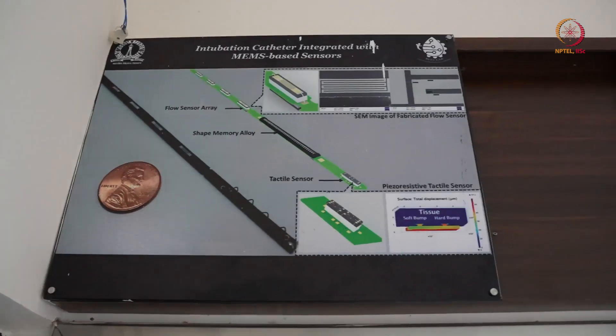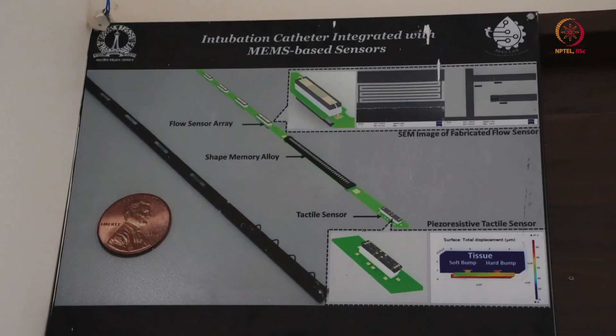Before going inside, from outside we will show some of the work that we have done using this facility. The first image discusses an intubation catheter integrated with MEMS-based sensors. Here we can see a flow sensor array and a tactile sensor which are used for understanding airway choking or airway obstruction. The flow sensor array was implemented by a series of heaters, and the tactile sensor is basically a resistive tactile sensor. These are integrated on a flexible PCB, and the force sensor and flow sensor array — basically the heaters — are fabricated in our facility.